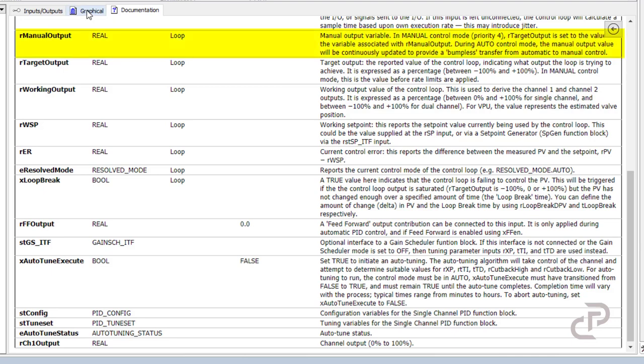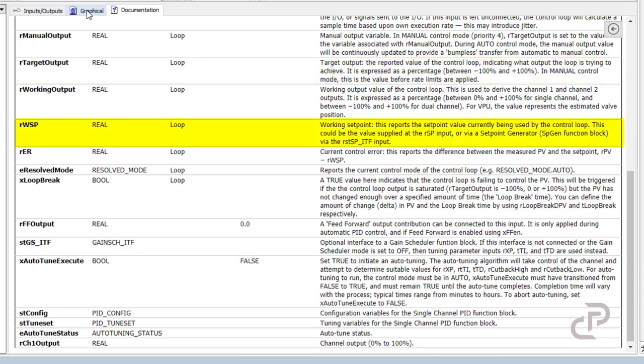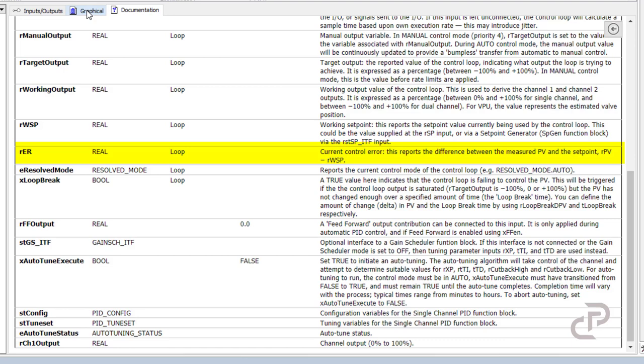The next one is the manual output variable. In manual control mode, the target output is set to the value of the variable associated with our manual output. Target output indicates what output the loop is trying to achieve, expressed as a percentage between minus 100 to 100. Working setpoint reports the setpoint value currently being used by the control loop. Current control error reports the difference between the measured process value and the setpoint.